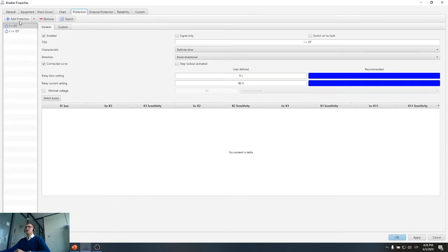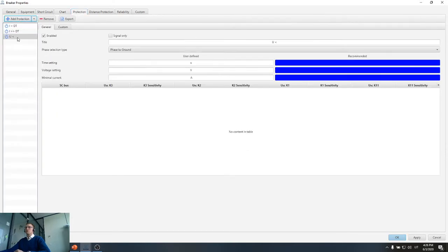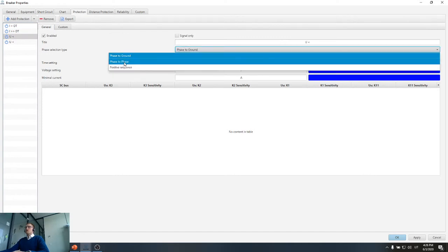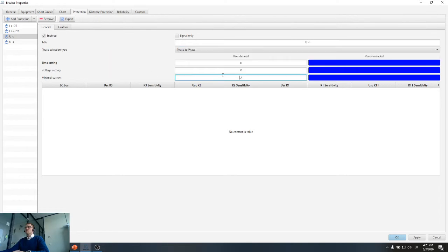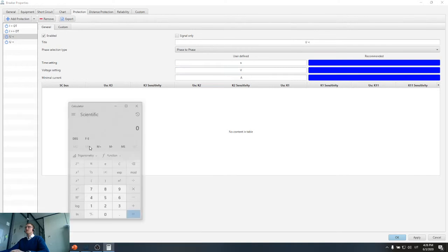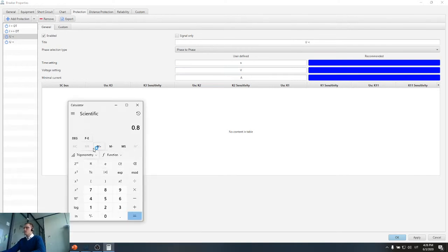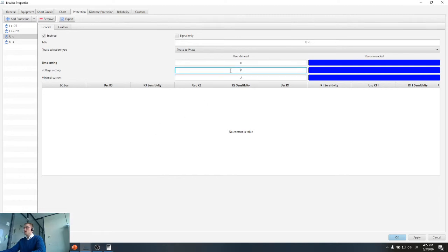So I will double click on the breaker and add one more numerical relay option, which is the under voltage relay. I will add two different stages for the under voltage relay. For the first stage, let's select that our numerical relay will measure phase-to-phase voltage. And let's say the voltage goes down by 20%, so the voltage will be around 5000 volts. Our relay should trip in, let's say, 15 seconds, for this motor, to avoid high inrush current during self-acceleration of the motor.